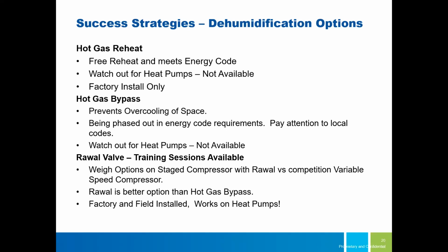They cost more money, and they have a higher MCA and MOCP, which is one of the most important things that go out in your drawings as a consulting engineer. So noting that a Rawal valve is a great option, better than hot gas bypass. You can factory and field install it, and it works on heat pumps if you want. So if you've got a heat pump, you're not going to be doing hot gas reheat or bypass.